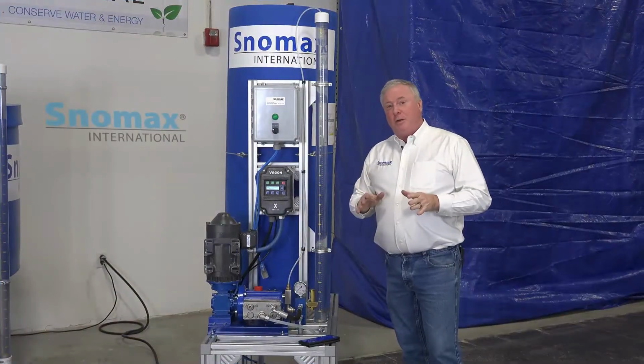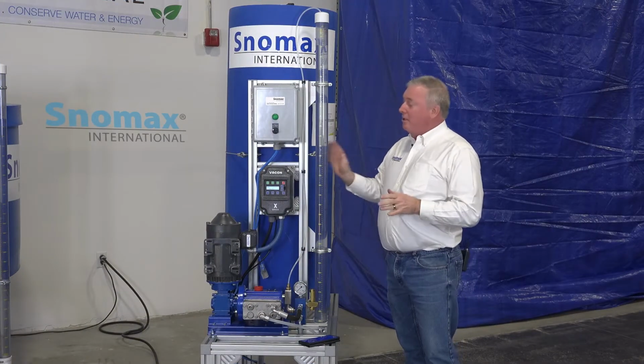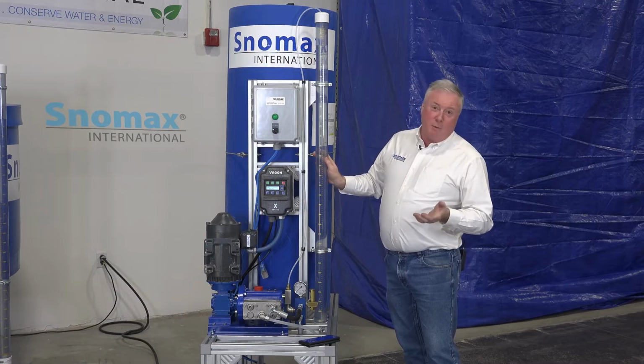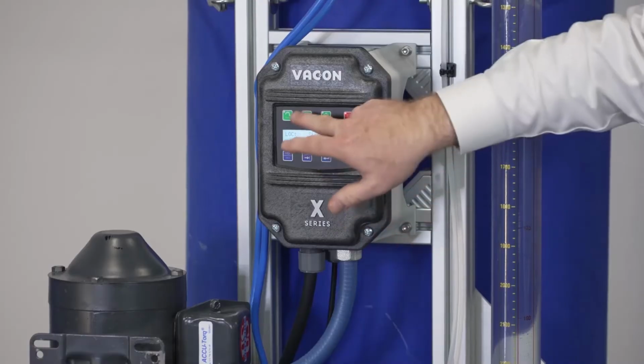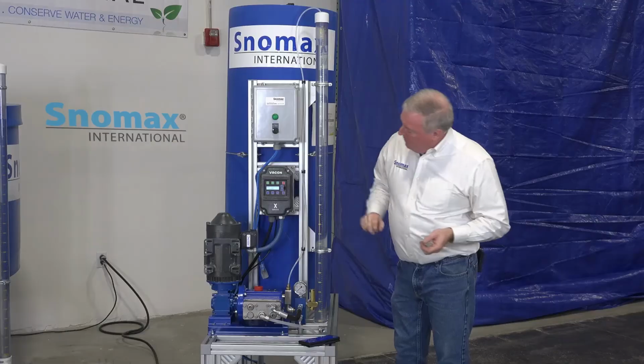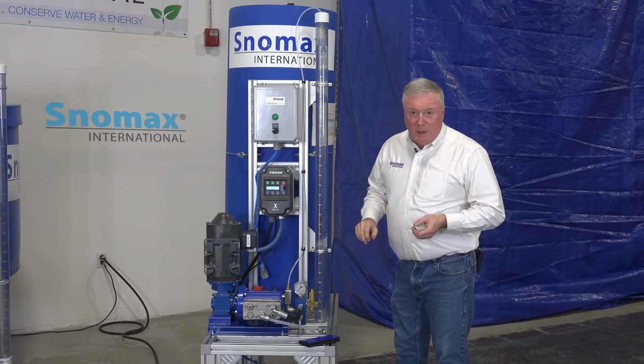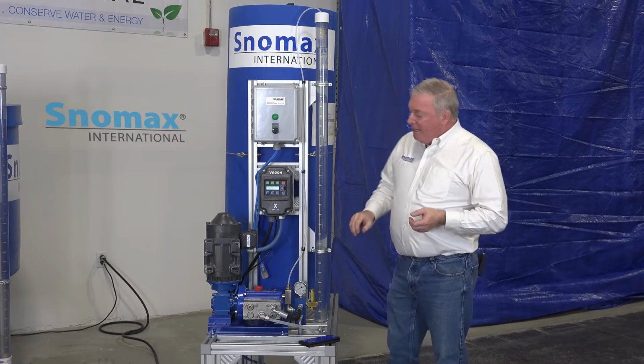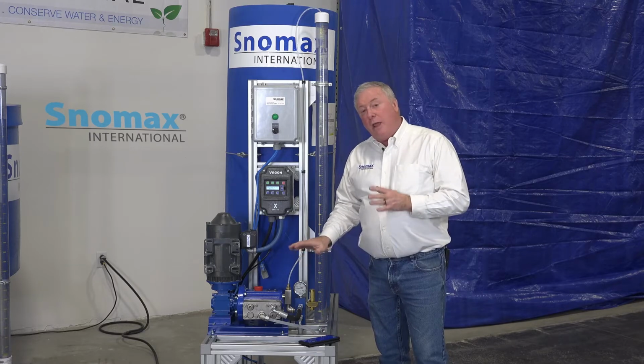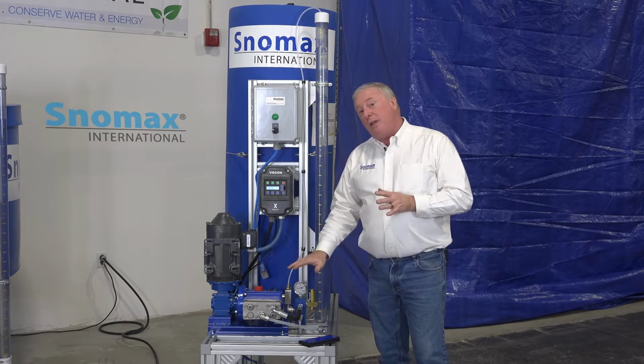The first system we're going to show today on how to calibrate is our smallest system. So step one is to get the pump running. So we're going to start the pump. Takes a second for it to come on. And then the next thing we need to do is make sure there's no air anywhere in the plumbing or especially the head of the pump.